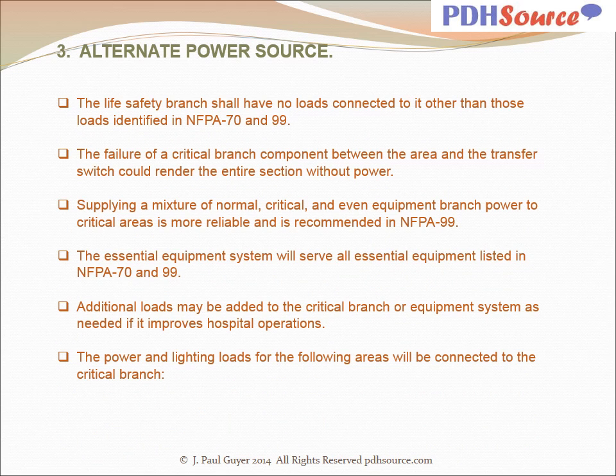The life safety branch shall have no loads connected to it other than those loads identified in NFPA 70 and 99. The failure of a critical branch component between the area and the transfer switch could render the entire section without power. Supplying a mixture of normal, critical, and even equipment branch power to critical areas is more reliable and is recommended in NFPA 99. The essential equipment system will serve all essential equipment listed in NFPA 70 and 99. Additional loads may be added to the critical branch or equipment system as needed if it improves hospital operations. The power and lighting loads for the following areas will be connected to the critical branch.